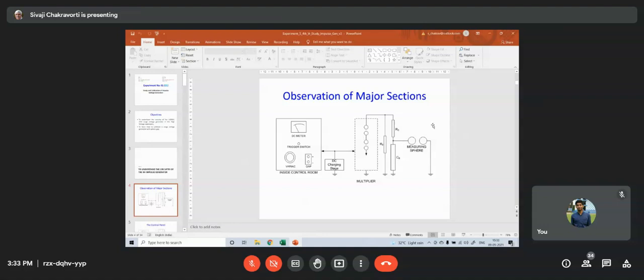I give you a problem, a real-life problem. Let's say I am testing an insulator. The insulator has to be tested as per Indian standards by 75 kV voltage. Now, I have to apply exactly 75 kV. I cannot do it with a less voltage because then I am doing a favor to this company. And if I do testing at a higher voltage, I am doing disfavor to this company. So both I cannot do. So I have to apply the voltage at 75 kV peak. But then how do I know that if I trigger this impulse generator at a certain DC voltage, I get 75 kV? That's precisely the calibration of the impulse generator.